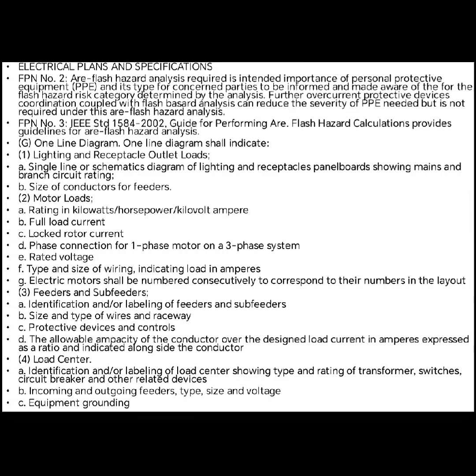FPN number 2. Arc flash hazard analysis required is intended to stress the importance of personal protective equipment, PPE, and its type, so that concerned parties are informed and made aware of the arc flash hazard risk category determined by the analysis. Further, overcurrent protective device coordination coupled with arc flash hazard analysis can reduce the severity of PPE needed but is not required under this arc flash hazard analysis. FPN number 3. IEEE Std 1584-2002, Guide for Performing Arc Flash Hazard Calculations, provides guidelines for arc flash hazard analysis.